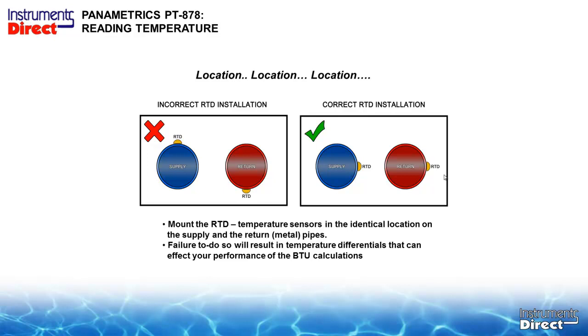For location of the sensor, we have to have the supply and the return doing the same. As you see illustrated, you're not going to mount your RTD on the supply at 12 o'clock and on the return at 6 o'clock. You could have a couple degrees differential on the same pipe if I were to mount a sensor here and a sensor here, because heat rises. So what we do is put the temperature sensor at 3 o'clock on both devices to minimize the temperature differential. And that's really all we're looking for, temperature differential. In this situation, you can have the best equipment in the world, but you get bad data, and you're going to calculate bad data as well.